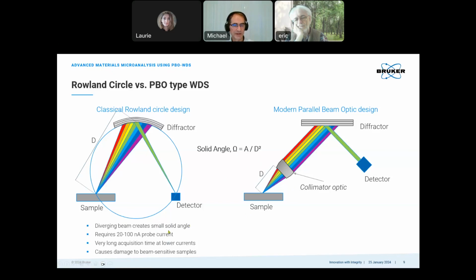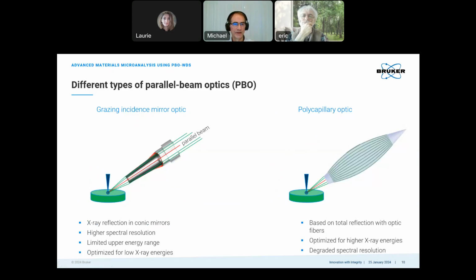So a classical system has a small solid angle. That means to have a sufficient signal, it requires a very high beam current or very long acquisition times. And both the long acquisition time and the high beam current may cause damage to sensitive samples. The parallel beam optic design guarantees a high solid angle with the optic close to the sample. That means in return, we can operate with very low probe currents, and the system is faster and causes less damage.